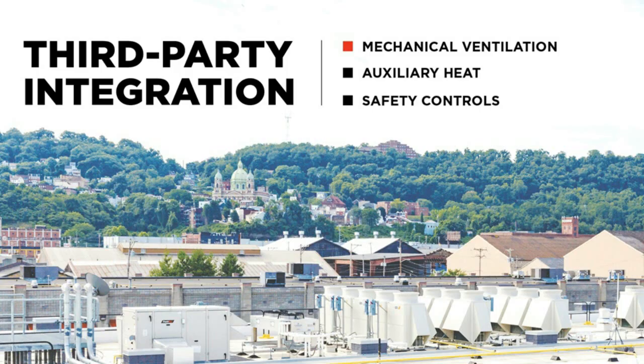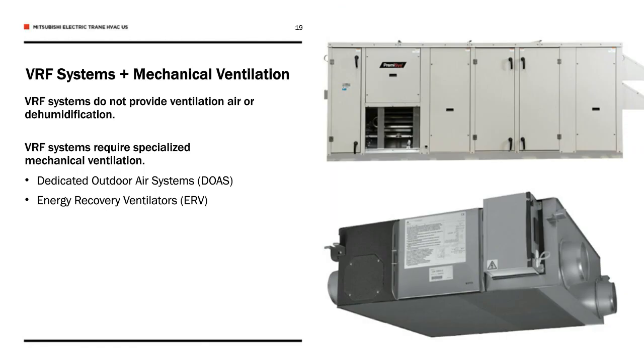So let's get into some of the specific systems and components that might be required when you have third-party integration, even if VRF is the main source of heating and cooling, as Kevin described. The first one we'll look at is mechanical ventilation. VRF systems inherently do not provide good ventilation or good dehumidification control. In this situation, a separate piece of equipment, such as a dedicated outdoor air system or an energy recovery ventilator, may be required.